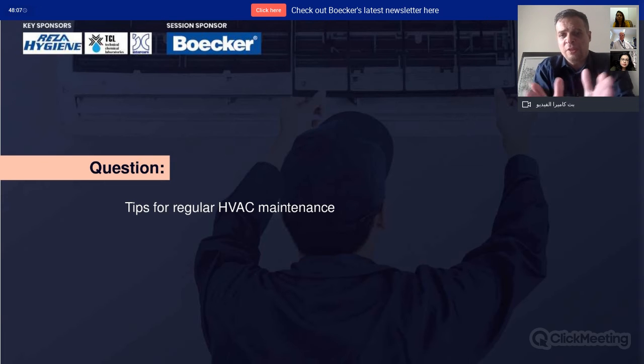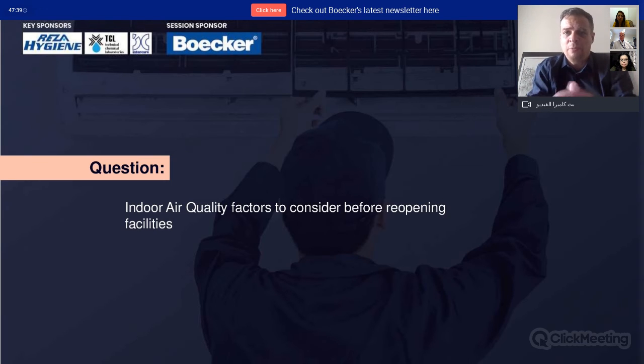What is very crucial is if you have buildings which have been closed down for a couple of days or a period of time due to lockdown, before you let people back in, run the HVAC system for at least 24 to 36 hours. During shutdown, a lot of dirt, dust, and pollutants settle in the ducts, and running the system for a while helps blow out this dirt.